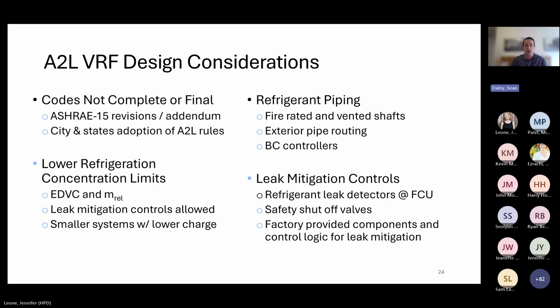And lastly, the leak mitigation controls will be fully plug and play from a factory perspective. We're providing all of the components and the control logic for the leak mitigation, so no additional control systems or components need to be specified. That's what we're looking at, at least from the Mitsubishi side of things, with the A2L systems. And next slide, please, Jennifer.